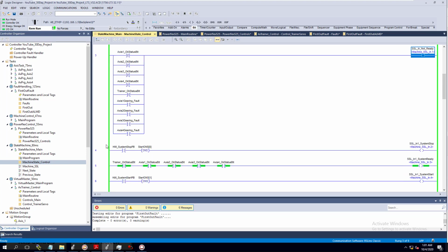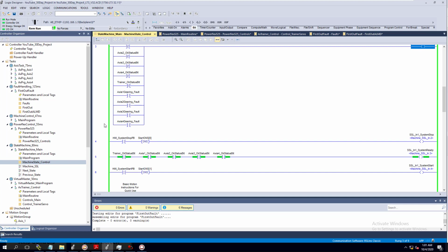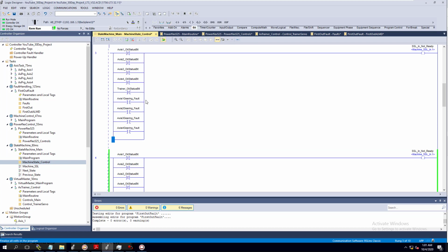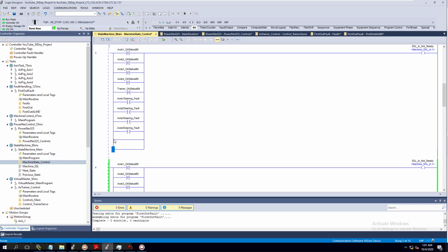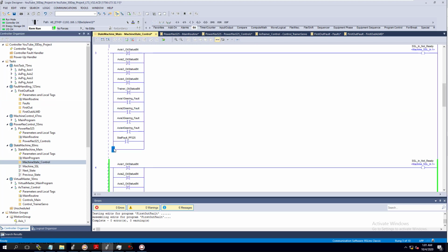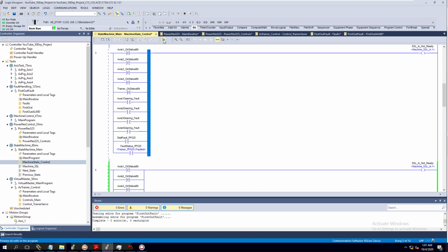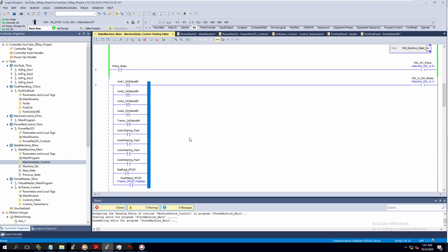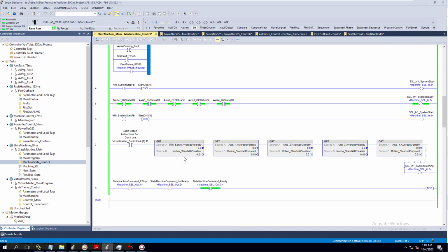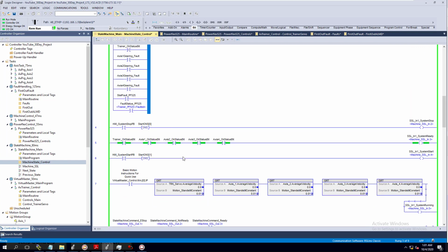And the not ready would be, let's do this, come in here and add the new rungs, because anytime we add something in, we're saying, hey, if it faults out, we definitely want to know about it. So let's go back here, and we're going to grab this fault, and we're going to go back to our state machine, and we're going to grab this fault, and that way if it faults out, it will shut the whole machine down. Because now if we're adding in another drive component, or just like we talked about before, we want to stop the system.